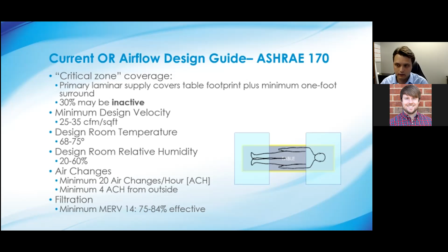To test that, we actually created an operating room in our office and designed it looking like this, with an 8-foot wide by 12-foot long array of HEPA filtered diffusers packed as tightly together as possible, basically creating a perfect design. We surrounded that array with lights and put booms in the light ring on the outside here. So we have 1 boom, 2 boom, and all of these diffusers have a HEPA filter within them. So we know we're delivering clean air right out of the ceiling. We're operating at about 25 air changes, so exceeding the ASHRAE standard in that sense. We're at about 27 feet per minute, so we're exceeding the standard in that sense. And essentially, we would call this an ideal perfect design, 100% critical zone coverage. We're not even playing with that 30% free area that you can get. We have the most ideal design possible.